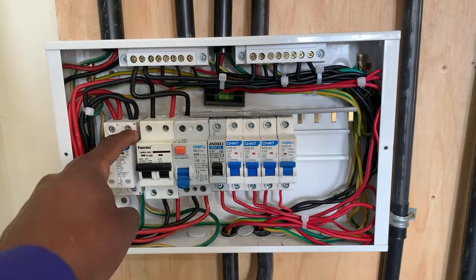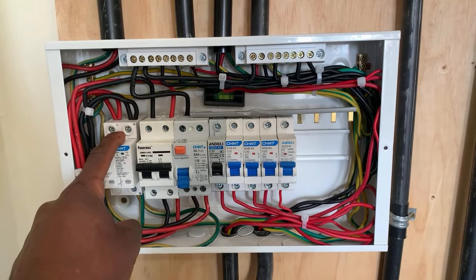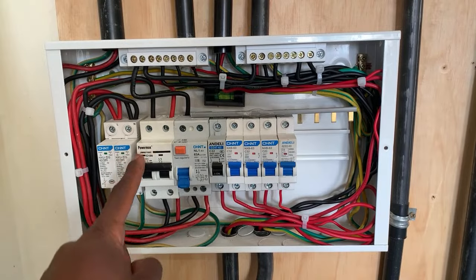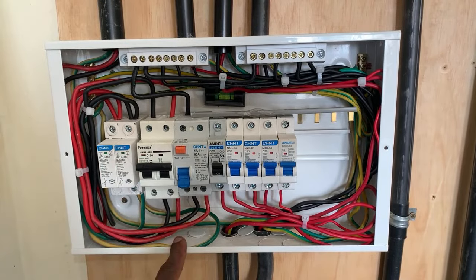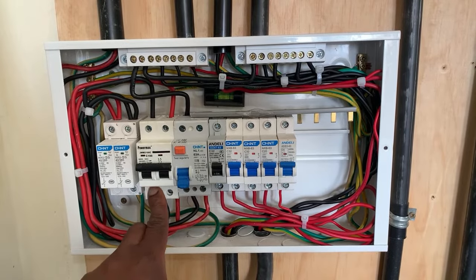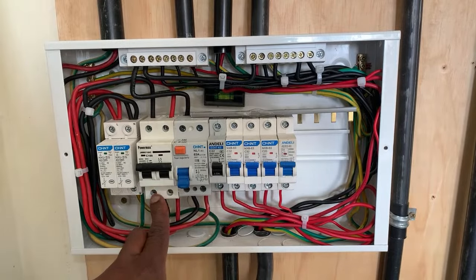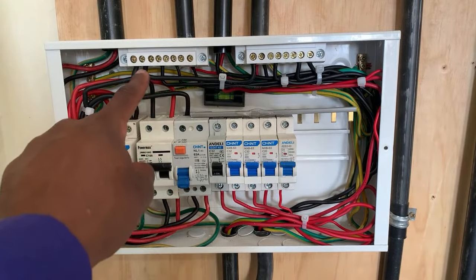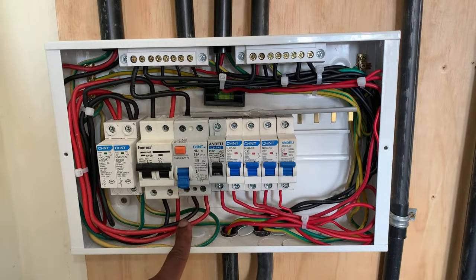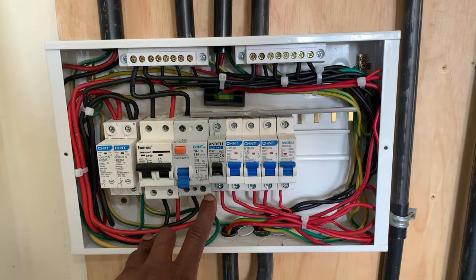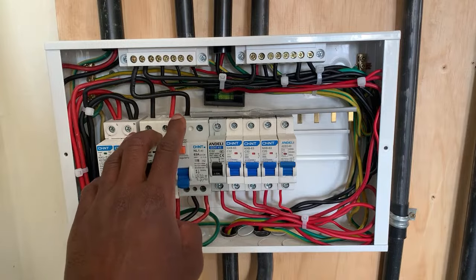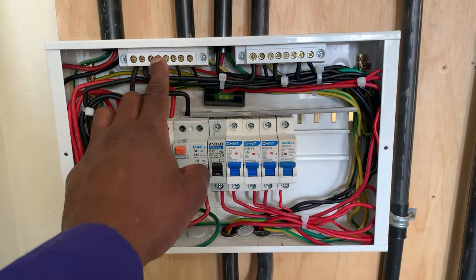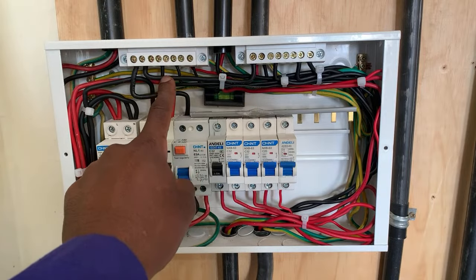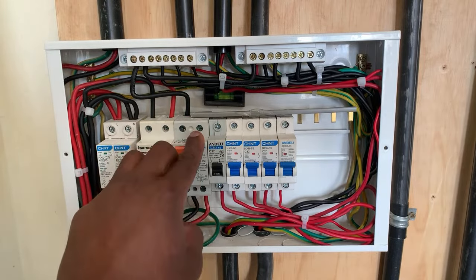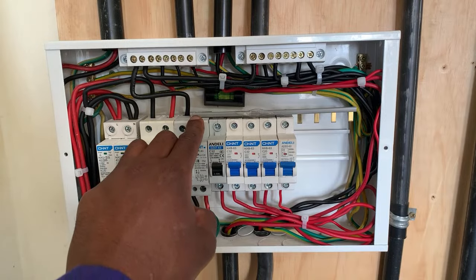From this, what I have here is the incoming live and the incoming neutral. From here, which is a loop, we have an output which comes all the way down to my main switch or my DP MCB. And then from the DP MCB, we have the output which goes all the way down to my RCCB. That is how I have wired it. So you see the neutral incoming in there, the phase incoming in there, and then I have my neutral going out to loop the neutral bars here. And on this phase side, on the live one, I have the live connected to the bar.